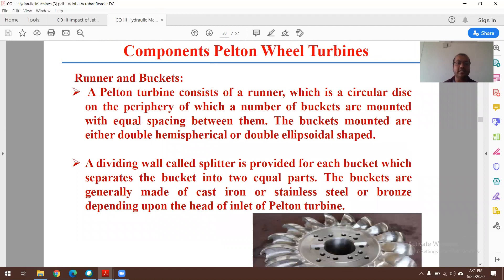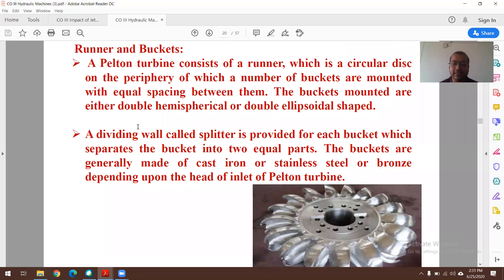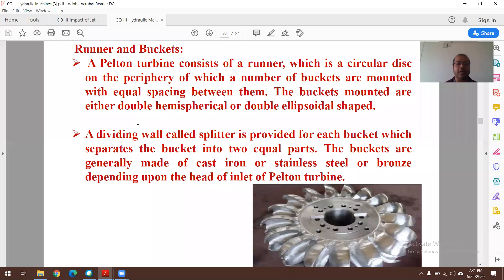A Pelton wheel turbine consists of a runner — a circular disc — on the periphery of which a number of buckets are mounted with equal spacing. The buckets are either double hemispherical or double ellipsoidal in shape. A dividing wall called a splitter is provided for each bucket, which separates it into two equal halves. Buckets are generally made of cast iron, stainless steel, or bronze, depending upon the head at the inlet of the Pelton turbine.